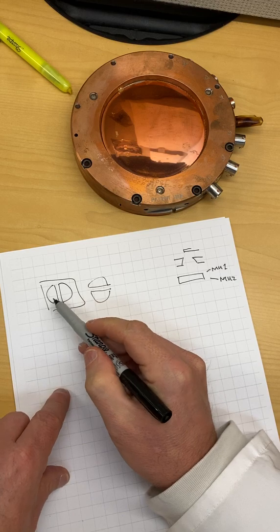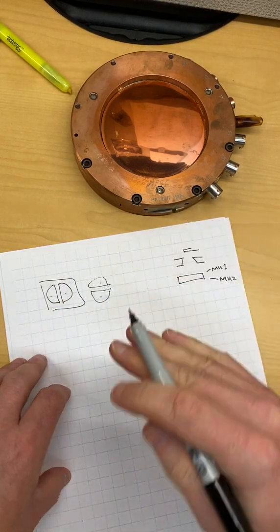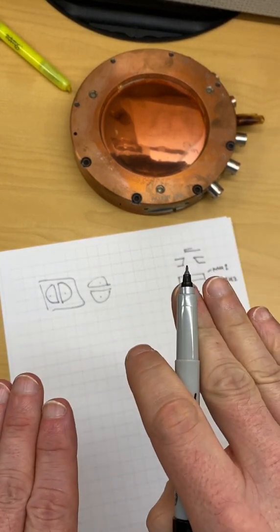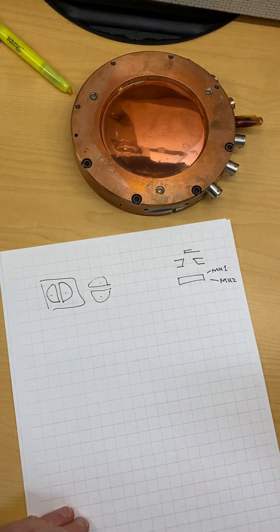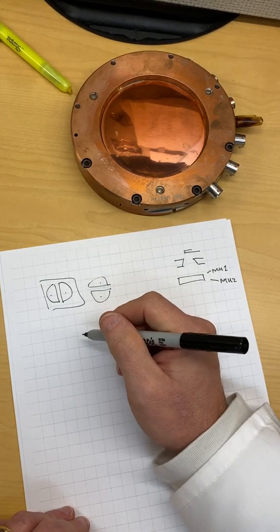And if the reading from one side - left side to the right side, to the upper to the lower - they get off a little bit, it knows that the beam is not flat anymore and it'll shut the beam off. And then it can also measure the symmetry of the beam.